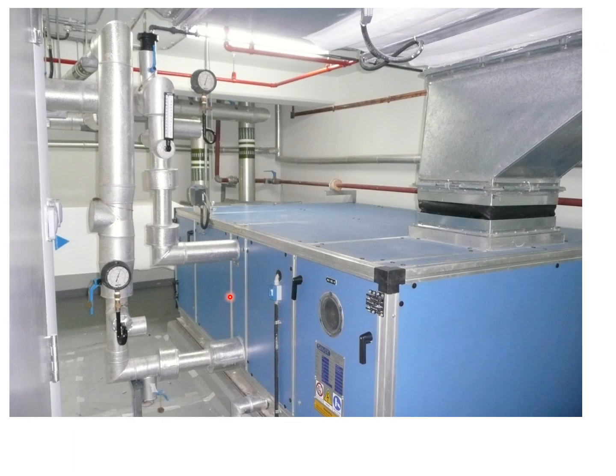So this AHU occupies an important space, and the AHU may be floor mounted or also ceiling mounted in size up to 17.5 ton. Below all that, one AHU is provided for a load up to 60 ton, beyond which you may have to provide two. All AHU rooms on different floors normally should be one above another.